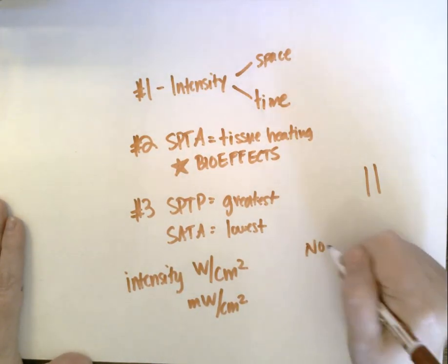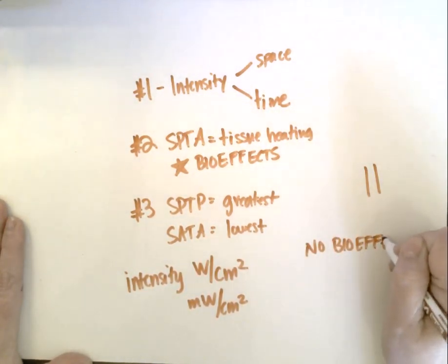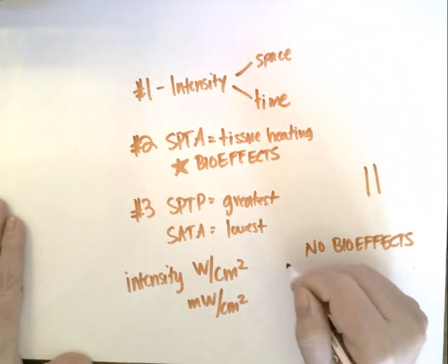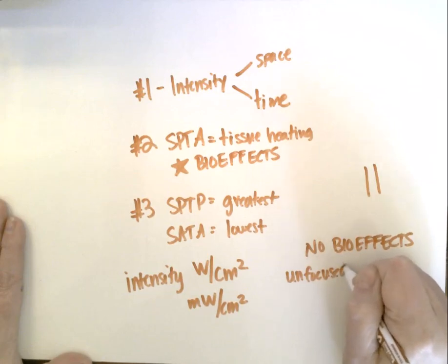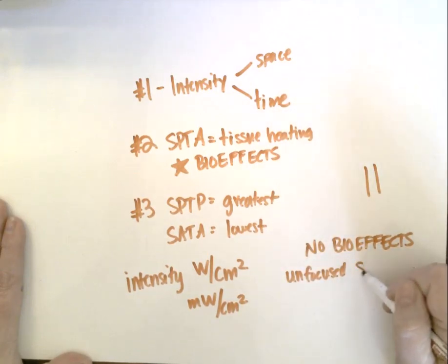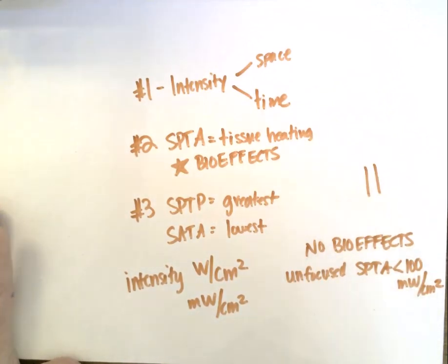So no bioeffects occur when we have an unfocused beam and the SPTA is less than 100 milliwatts per centimeter squared.